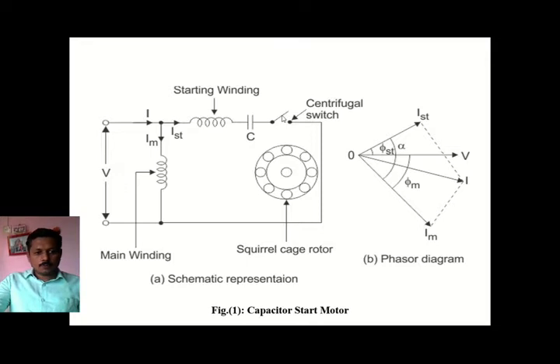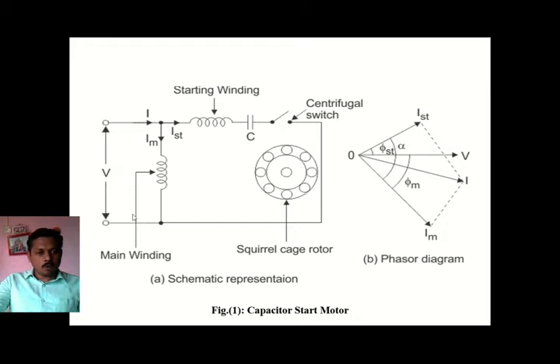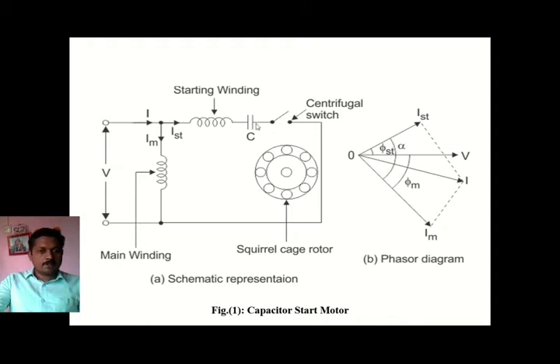The centrifugal switch operates once the motor reaches 70 percent of its rated speed. It will open and remove the auxiliary winding from operation, and the motor will then run on only the main winding and rotor. So the starting winding and capacitor are placed in series with each other.